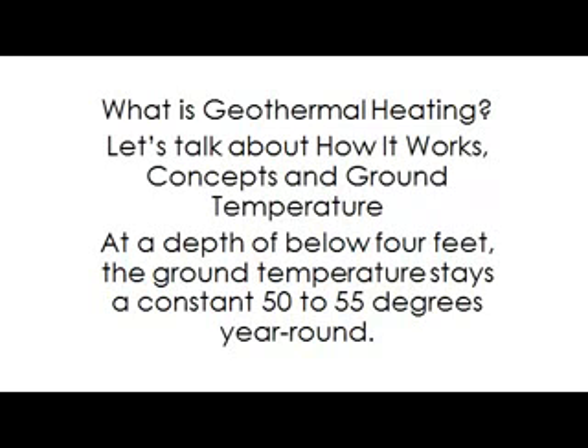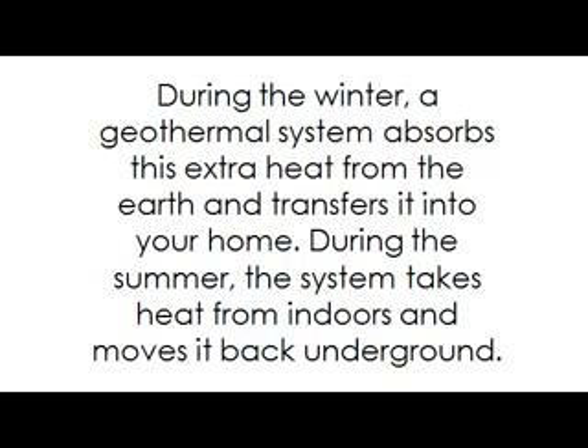What is geothermal heating? Let's talk about how it works, concepts, and ground temperature. At a depth of below 4 feet, the ground temperature stays at a constant 50 to 55 degrees year-round. During the winter, a geothermal system absorbs this extra heat from the earth and transfers it into your home. During the summer, the system takes heat from indoors and moves it back underground.